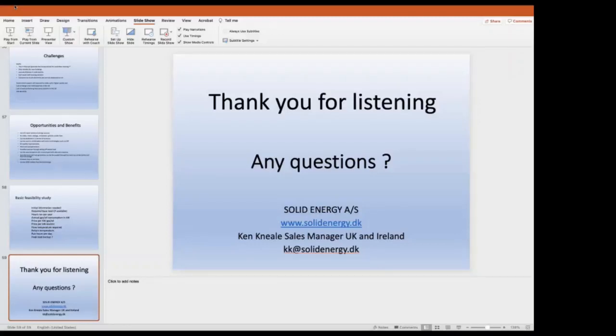Yeah. Great. Question from Matthew. Would SCOP, which is seasonal COP, be a more relevant figure to use rather than instantaneous COP? Yeah, in any measurement of efficiency, you have to look upon it at 12 months. I can say under certain circumstances, we can get a COP of 4.5. But if that's only when it's 18 degrees out and the sun's shining, that is mis-selling and taken to its extreme.